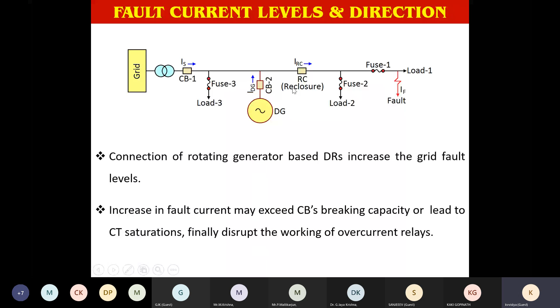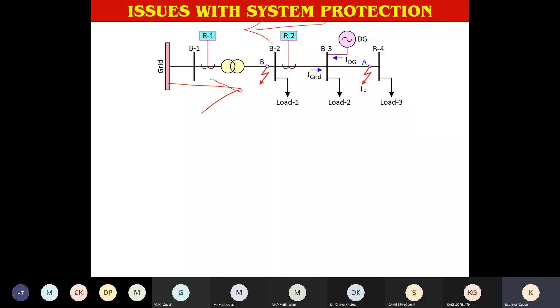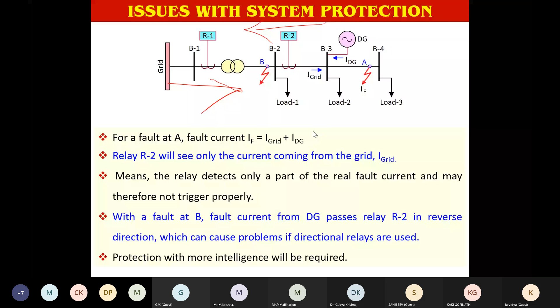Then comes the fault level, because the original system is designed for a particular current level. And when you incorporate more resources, naturally the fault level will increase. Then the protection. Normally, wherever relays are incorporated, these are all directional relays, because current flows only from one direction, from this direction. This is the direction of the normal current flow or fault current flow, because we never anticipated any generator in the downstream. But suppose you have incorporated a solar PV or wind turbine on the load side, naturally there is a possibility of current flowing in the other way also. So for some directional relays, fault current in the downstream of that relay may not be reflected. That means the fault may not be detected. So the designer has to take care of that. So when you are incorporating renewables in the oldest system, it will be a tough situation. But of course, in the latest design, everything will be taken care of.